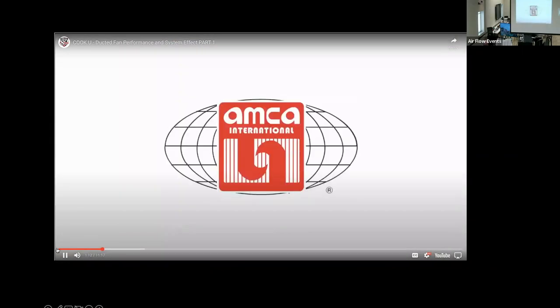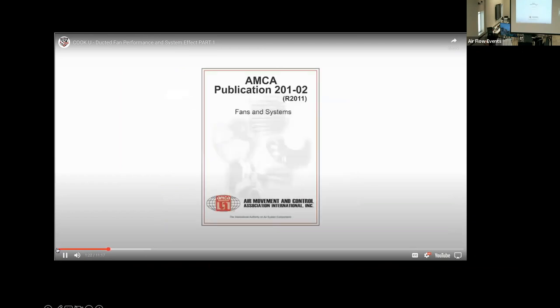How important is the length of the discharge duct? Let's take a closer look. AMCA, the Air Movement and Control Association, establishes test standards for fans and a certified rating program that ensures uniformity in fan testing. AMCA Standard 201 shows why discharge duct length is important.